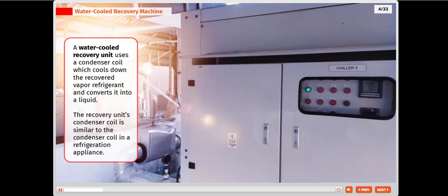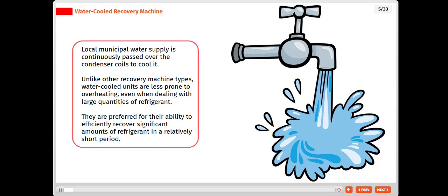A water-cooled recovery unit uses a condenser coil which cools down the recovered vapor refrigerant and converts it into a liquid. The recovery unit's condenser coil is similar to the condenser coil in a refrigeration appliance. Local municipal water supply is continuously passed over the condenser coils to cool it. Unlike other recovery machine types, water-cooled units are less prone to overheating, even when dealing with large quantities of refrigerant. They are preferred for their ability to efficiently recover significant amounts of refrigerant in a relatively short period.